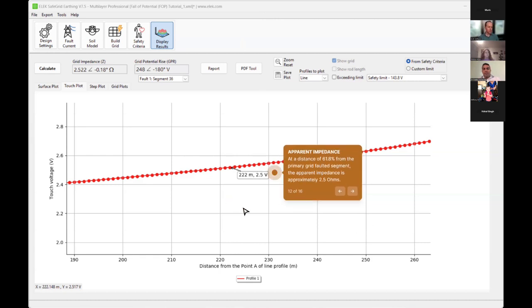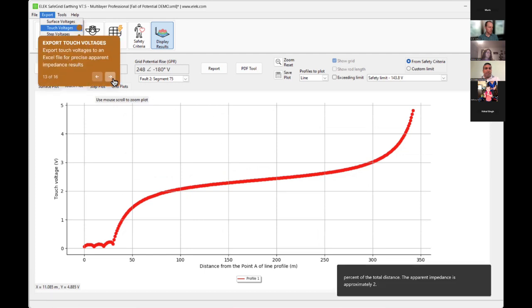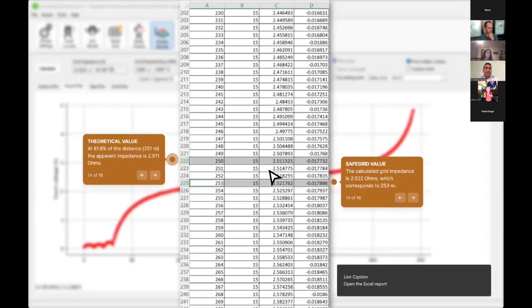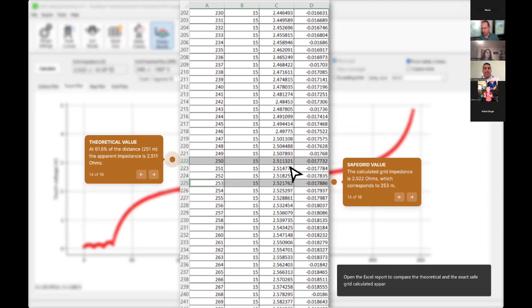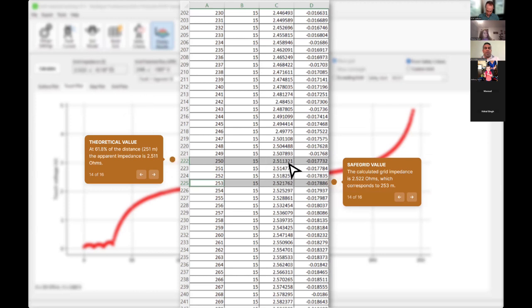So at a distance of 220 meters, we get 2.5 volts, which is the ground surface voltage. Since the current is 1 ampere, we would obtain 2.5 ohms, which is very close to the grid impedance that has been calculated. If you download all the potentials and look at them, we see that we get the exact grid potential, 2.511, which is very close to the 2.5 we calculated. It's between 250 and 253 meters, very close to the 61.8% that the theory says.